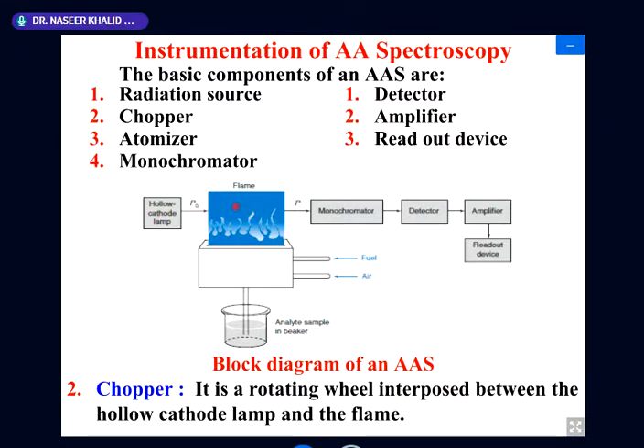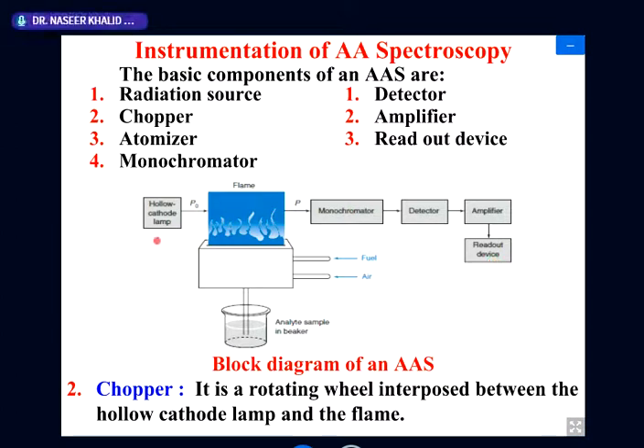The radiation from the radiation source passes through the system. The difference between the initial intensity and the final intensity is recorded, detected, amplified, and read out. In between the radiation source and the atomizer, there is a chopper.